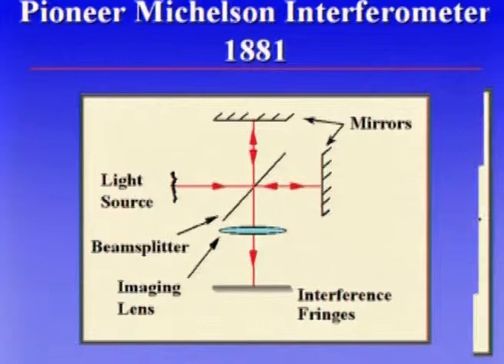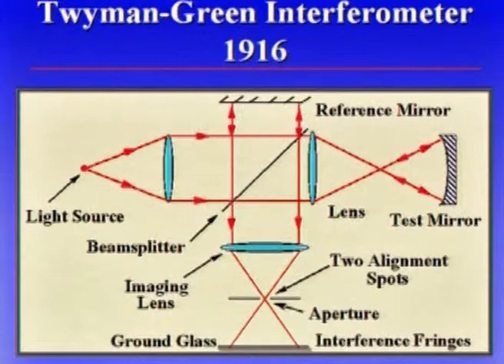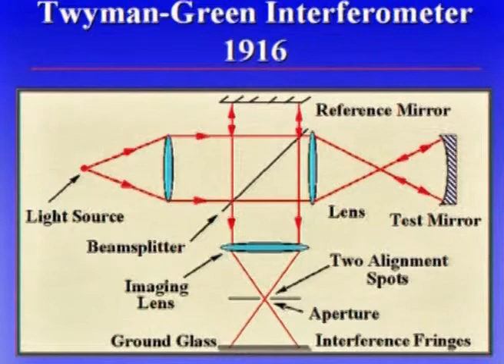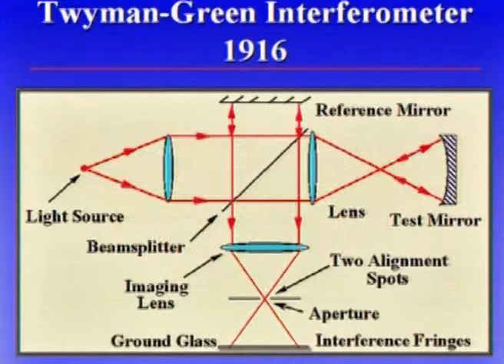Twyman and Green took what was basically the Michelson interferometer and used a small source instead of the large source Michelson used, and they got a patent on this in 1916. They used this technique for testing lenses, testing mirrors, testing prisms, and so on. The basic idea: light comes in, you have a reference arm, light goes up to the reference arm and back, and light goes to whatever you're testing. You'll get interference fringes that tell you how the optics depart from the right shape. So that's 1916.